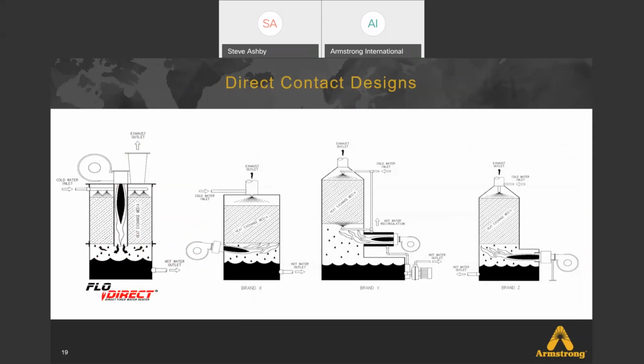Okay, this just gives you a further insight into the internals of the heater and some different options out there as far as different designs. Our heater here on the left, we're the only one, as you'll see, that has the burner and blower that sits on top of the heater and then fires vertically downward. You'll also see in what we call a flame tube, that flame shoots vertically downward through the central part of the heater body, and you can see there's a piece of pipe there.